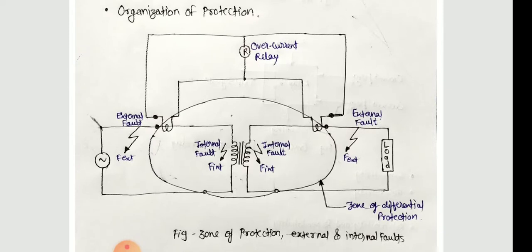The protection must be organized in a very logical fashion. The idea is to provide a ring of security around each and every element of the power system. If there is any fault within this ring, the relays associated with it must trip all the allied circuit breakers so as to remove the faulty element from the rest of the power system. This ring of security is called the zone of protection.